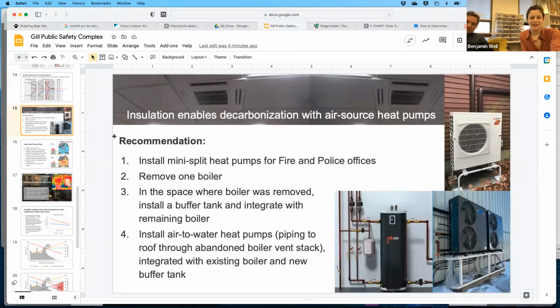And another change that insulating will enable is decarbonization by switching over to air source heat pumps for heating and cooling. Our recommendation is to install mini split heat pumps for the police and fire offices. And since this two-boiler system is oversized, remove one boiler, and in the space where the boiler was removed, install a buffer tank and integrate it with the remaining boiler, and then install air-to-water heat pumps that are integrated with the existing boiler and the new buffer tank. So basically keeping the same heating distribution system, just having a new way of generating the heat that gets distributed. And also, in one step, solving the problem of not having cooling.